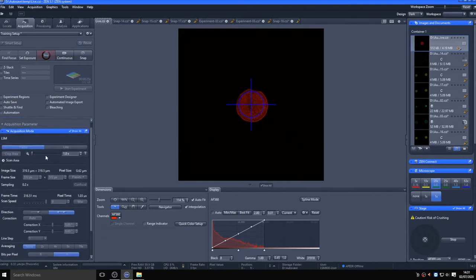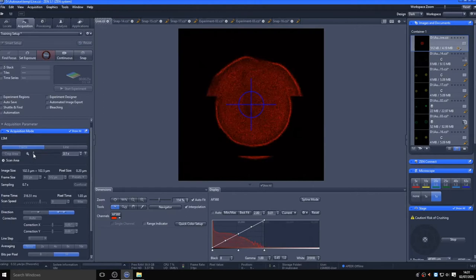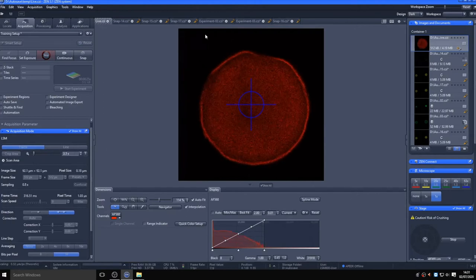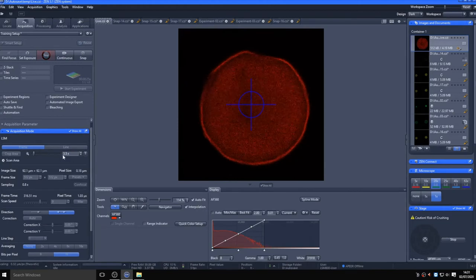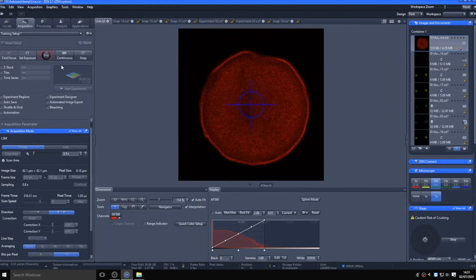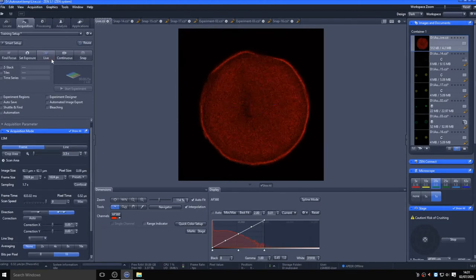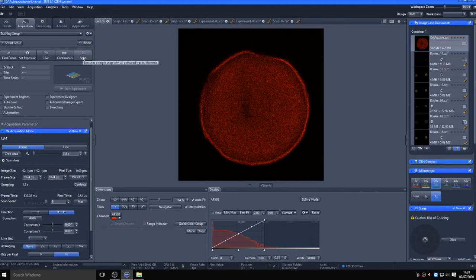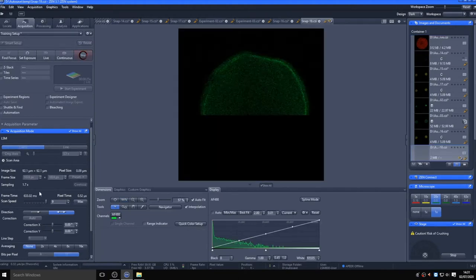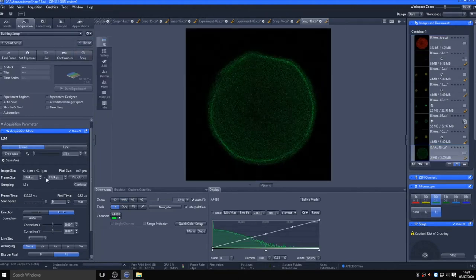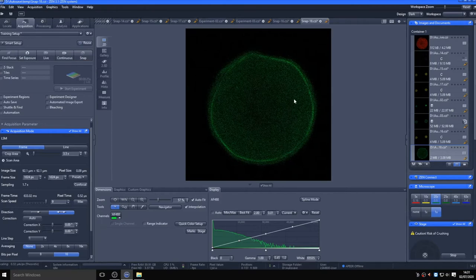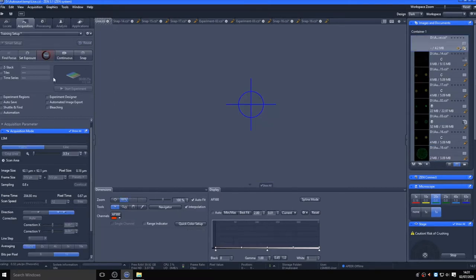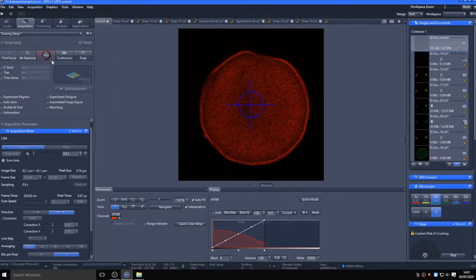In order to make imaging your sample more efficient, it is possible to utilize the option of confocal zoom to increase the magnification of your image so that you are not imaging the area around your sample. This is done in acquisition mode and is essentially the same as taking the one-times image and cropping the resulting image. Whilst this does not gain you any resolution, it does have the benefits of reducing acquisition time and means that you are not bleaching any cells around the one you are currently focused on.